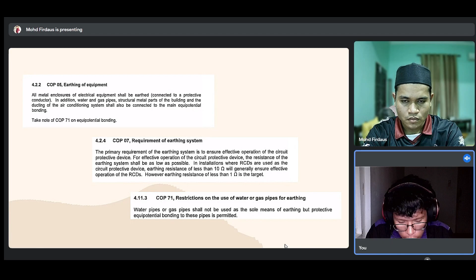We can also relate this to COP71, which restricts the use of water or gas pipes for earthing. The question also asked about connecting the earthing to a water pipe connected only to the public water supply. COP71 states that water pipes or gas pipes should not be used as the sole means of earthing, but protective equipotential bonding to these pipes is permitted. That answers the question, following COP71.